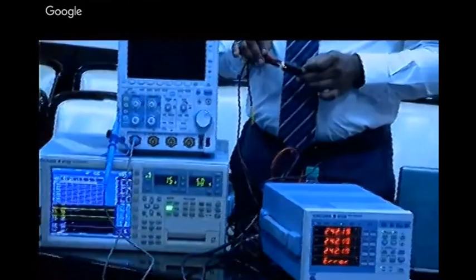So then what is the energy? Energy is nothing but watt hour. So there is an integration mode here. If you switch on that integration, it will calculate the total cumulative power with respect to time. So that will become the watt hour. For energy content, WH. Once it goes above 800 watt, it will start showing 0.1 kilowatt, 0.2 kilowatt, so it will become kilowatt hour. Show the frequency. It is 49.8. Change the update rate, slow it down.